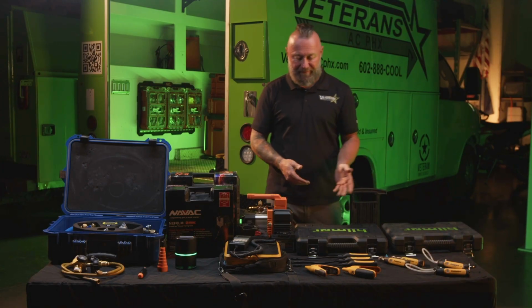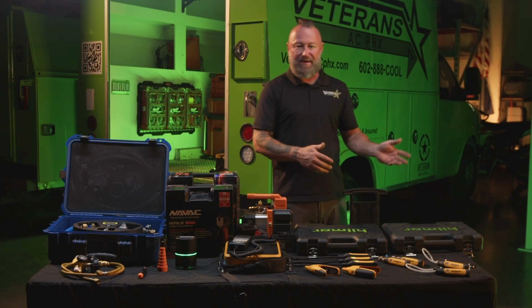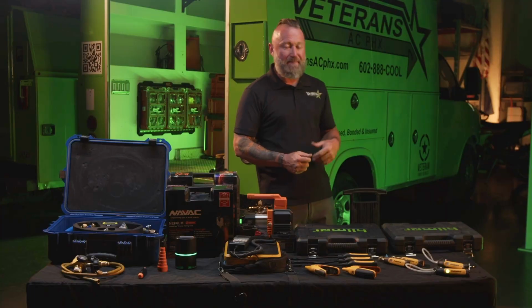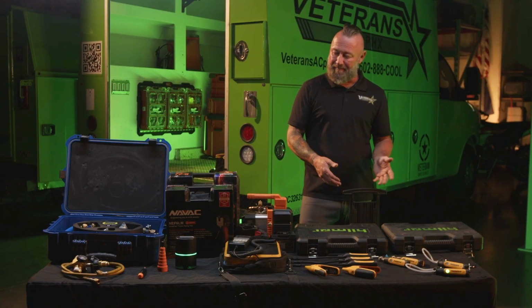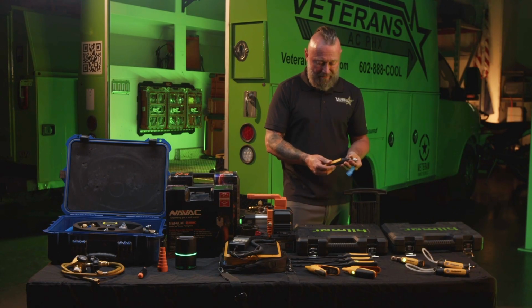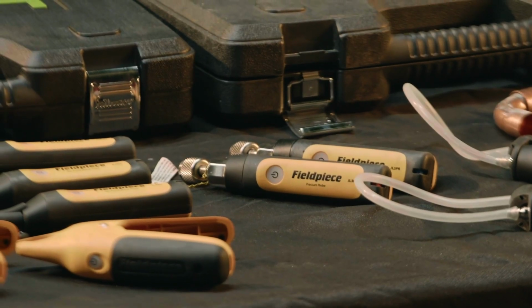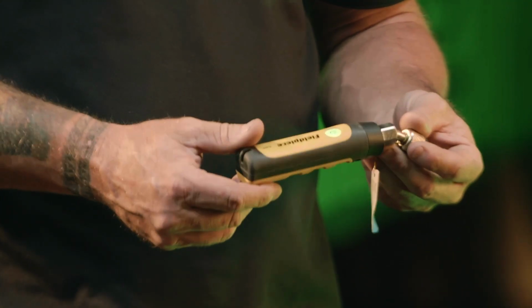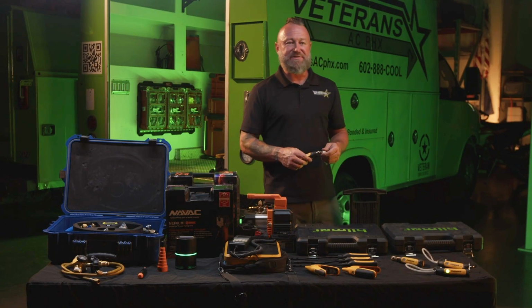When we come in and deploy the Fieldpiece probe package, it's a night and day difference, and it's a game changer, right? The amount of data that this collects compared to the traditional gauges, there's no comparison whatsoever. So the numbers don't lie. On your outdoor unit or package unit, you're going to have your king valves or just service ports. These are going to connect on the suction side and the liquid side. Depends on the freon. Each freon is going to have different design pressures.